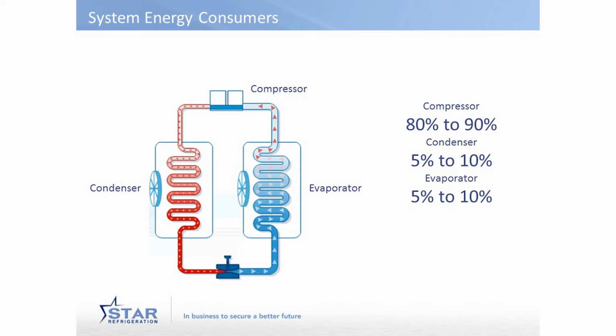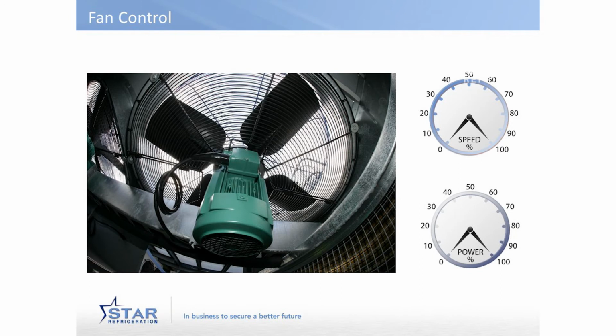With reciprocating compressors, it's a little bit different. If you're on part load, the efficiency of the compressor can actually improve because you're using the full heat exchanger surface on the condenser and the evaporator, but only doing part of the cooling process. So this would be a typical screw compressor type curve of, on the side here, coefficient of performance, which is essentially how efficient is the plant. You see good efficiency where we're at 100%, but it's tailing off as we drop off in capacity. If we were to use an economized compressor, then it's kind of better initially, but tails off again. What that means is if we're using a VSD, we can make the plant more efficient, better COP, down to about 50% load, and then it starts to fall off as we go below 50%. Whereas with a slide valve, we're dropping from day one.